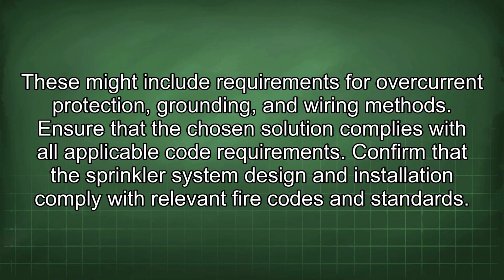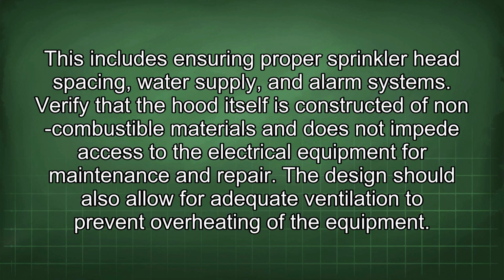Confirm that the sprinkler system design and installation comply with relevant fire codes and standards. This includes ensuring proper sprinkler head spacing, water supply, and alarm systems. Verify that the hood itself is constructed of non-combustible materials and does not impede access to the electrical equipment for maintenance and repair. The design should also allow for adequate ventilation to prevent overheating of the equipment.